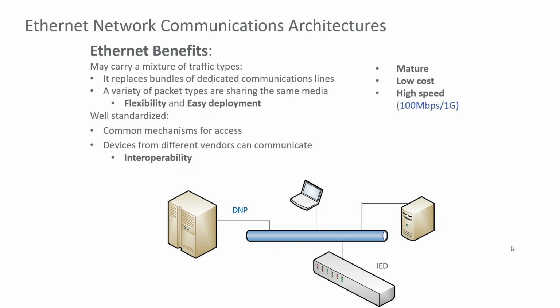So what are some of the benefits of using Ethernet? One big advantage is it supports multiple protocols on the same data pipe or physical data link. Remember, serial only supports one protocol - so if you needed SCADA information and then needed to connect to the relay for diagnostic information that didn't support DNP, you'd need another serial link to that device. With Ethernet, all protocols can be supported.